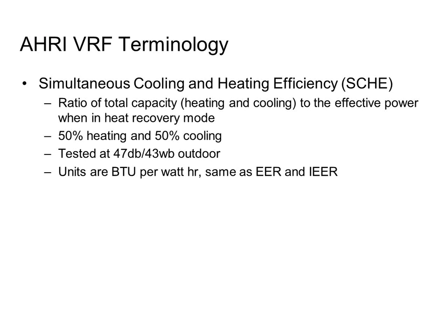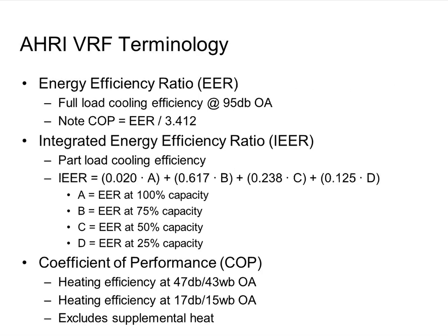Andrew asks if the IEER weighting is the same for other technologies, and no, it is not. It seems like all the manufacturers, whether it's the chiller group, the DX group, or the VRF group, have slightly different weighting factors on these capacities that I'm showing here. They're close. They do heavily weight the 50 and 75 points, and they put very little weight on the 100 and 25% weighting points. But the exact weighting multipliers are not identical to other technologies, but they're close.